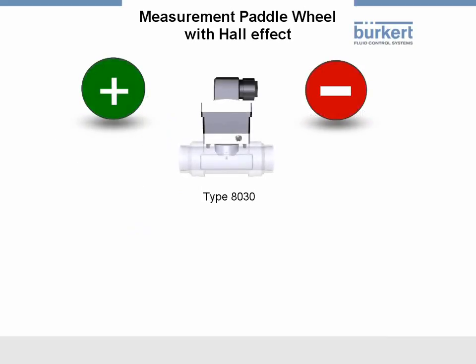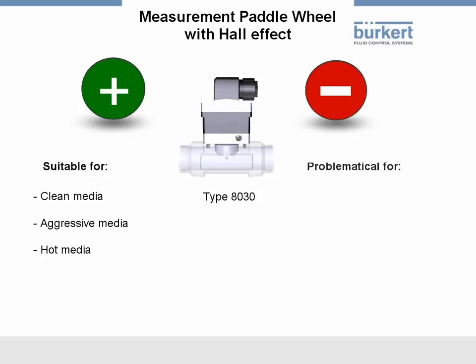The flow measurement with a paddle wheel and Hall effect sensor is suitable for clean, aggressive, and hot media. The medium should contain no hair or fibers, since they can hinder the paddle wheel or bring it to a standstill. Ferromagnetic particles in the medium should also be avoided.